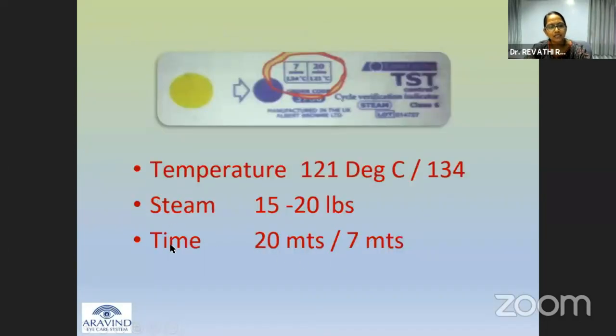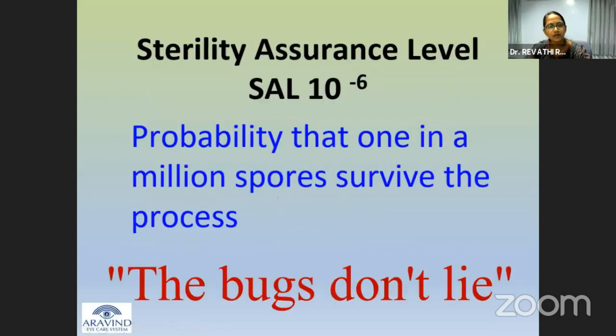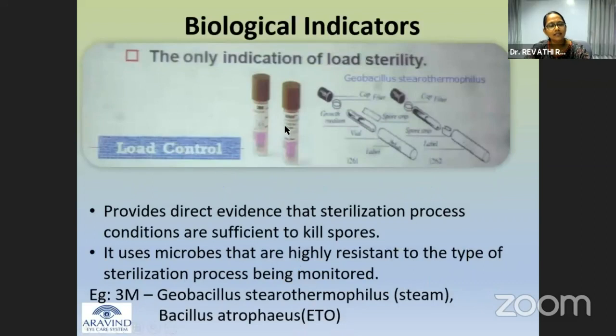TST, again temperature, steam and time, all 3 critical parameters are covered in this class 6 emulating indicator. So the sterility assurance level has to be maintained within 10 to the power of -6. That means the probability that 1 in a million spores survives the process. But even so, the bugs don't lie, and this can be picked up easily through the biological indicator. So this is an ideal method through which the load sterility can be proved.